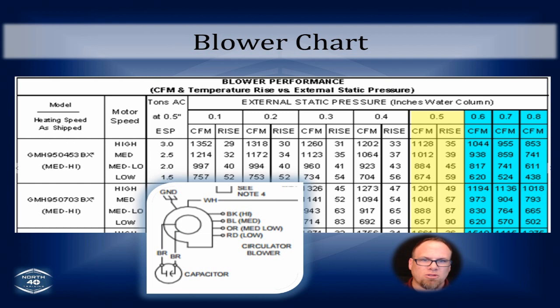So instead of lowering the blower speed like you should to the correct CFM value, you go out and add refrigerant to the system outside. When you add refrigerant, it fills that coil a little bit more and creates a little bit better temp drop. Never perfect, but it gets to the point where it's working fairly well. But over the long haul, here's what happens. It doesn't dehumidify properly. You've now overcharged the system, so it's not running efficiently. You've ruined some of the capacity, some of the efficiency. The compressor is not running, electrically speaking, as efficiently as it should. It's going to draw more amps on startup, so the likelihood of it tripping a breaker or blinking the lights is much higher than if you'd done it the way you should have.